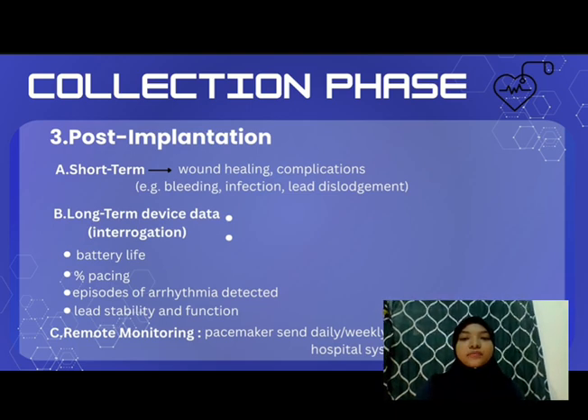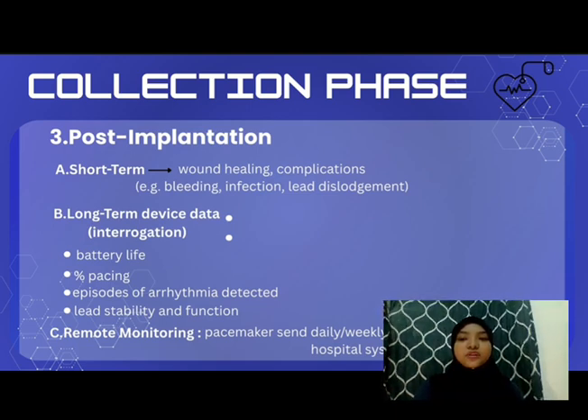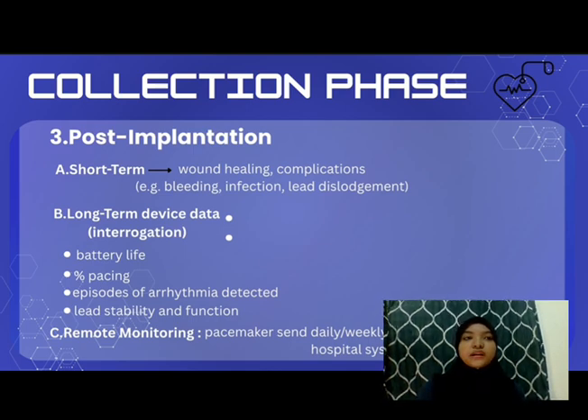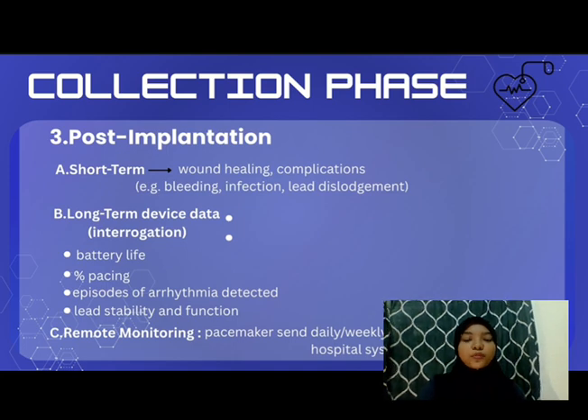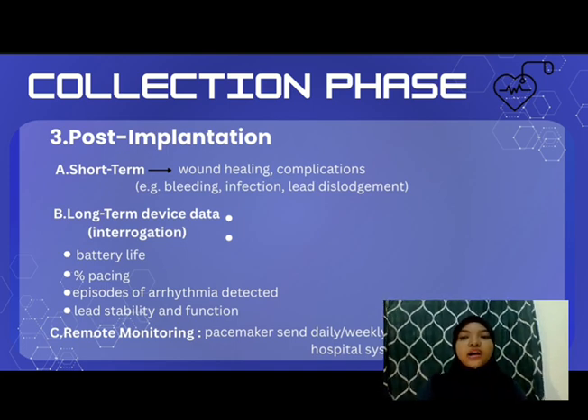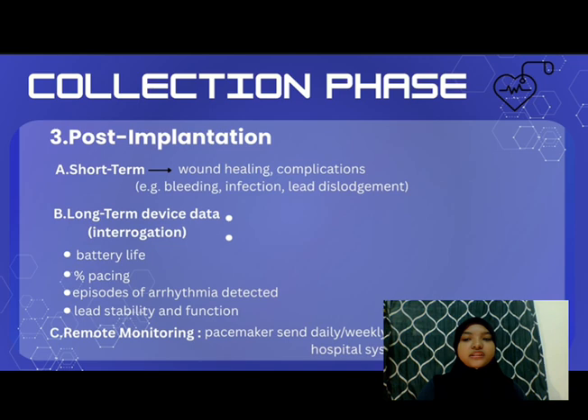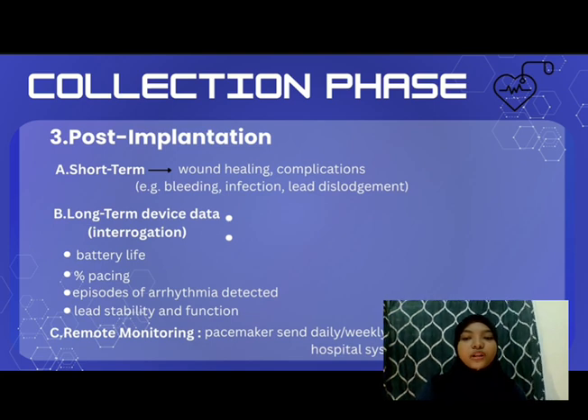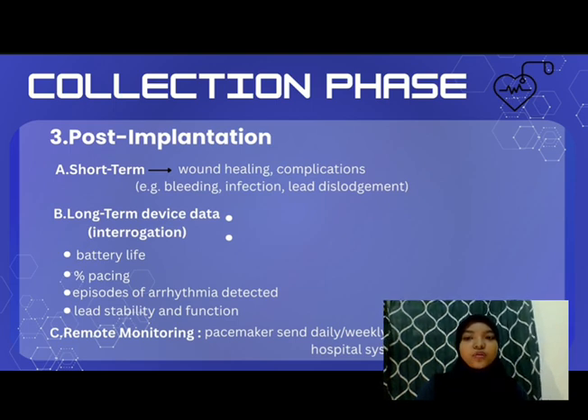Second is long-term device data interrogation. Over time, the pacemaker is checked regularly using a specialized programmer that communicates with the device. This process, called interrogation, provides detailed information such as battery life to estimate how long the device will continue to function before replacement is needed. Second is percentage of pacing, showing how often the pacemaker is supporting the heart compared to the heart's natural rhythm.